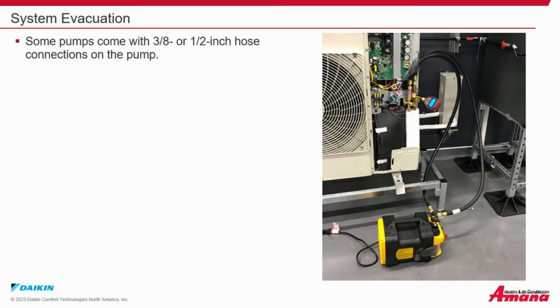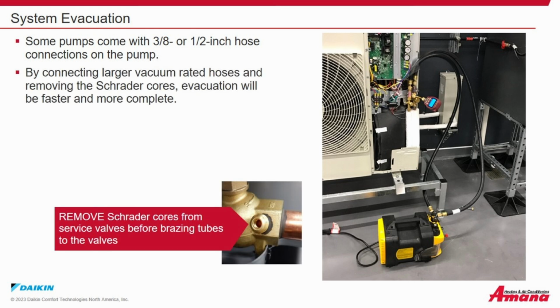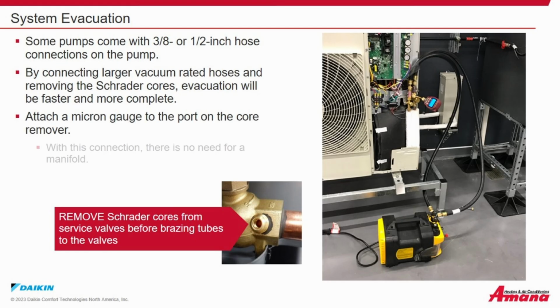System evacuation. Some vacuum pumps come with 3/8 or 1/2-inch hose connections on the pump. By connecting larger vacuum-rated hoses and removing the Schrader cores, evacuation will be faster and more complete. Attach a micron gauge to the port on the core remover. Again, remove the Schrader cores from the service valves before brazing tubes to the valves to prevent damage to the valves.